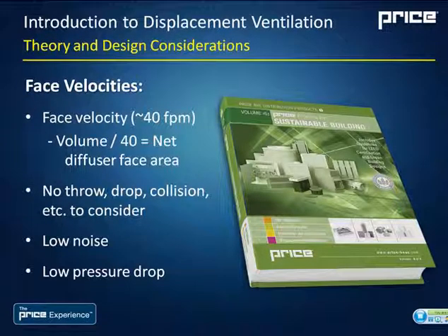So the final consideration with sizing and layout of diffusers is selecting a face velocity. ASHRAE recommends a face velocity of around 40 feet per minute for optimal comfort. And basically all you have to do is take the CFM that you calculated through our software or through the design procedure that we lay out in our green catalog, and divide by 40, which would get you your diffuser area that you require. From there, all you need to do is decide how many diffusers you want to place in the room, and where you would like to place them.